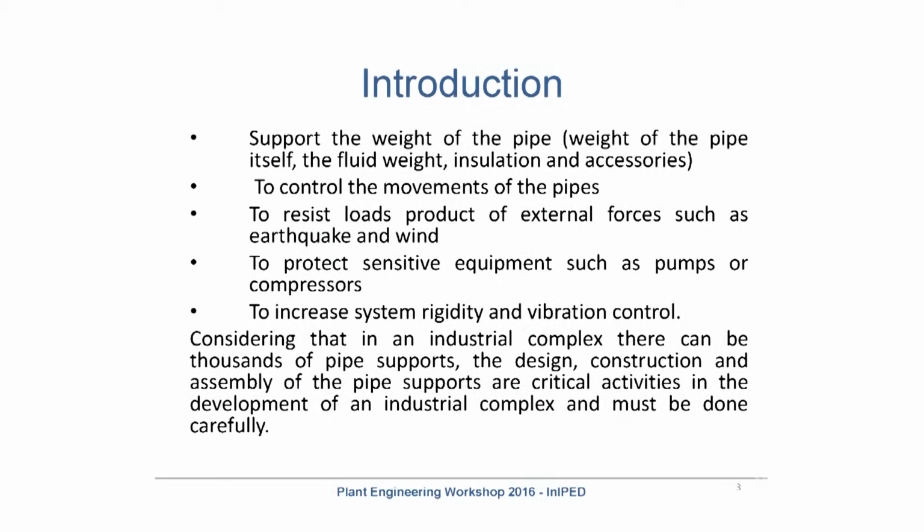So it's very important not only to perform the stress analysis correctly, it's also very important to perform the support design correctly. The support must be placed in the location that has been specified by the stress analysis, and I must also correctly design the type of support that I'm designing and constructing, to represent or restrict the degrees of freedom that the stress analysis requires.